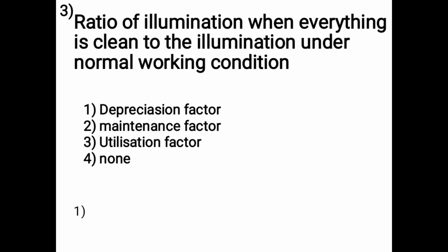Then third is ratio of illumination when everything is clean to the illumination under normal working condition. It is called the depreciation factor. Depreciation factor is defined as the ratio of illumination when everything is clean to the illumination under normal working condition. And the ratio of illumination under normal working condition to the illumination when everything is clean is the definition of maintenance factor.